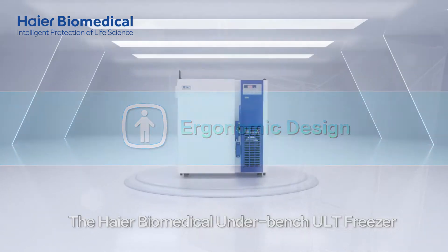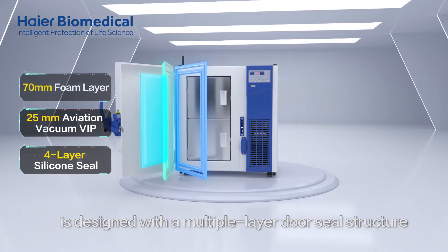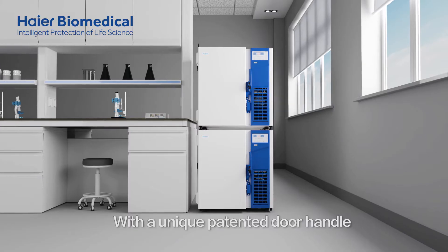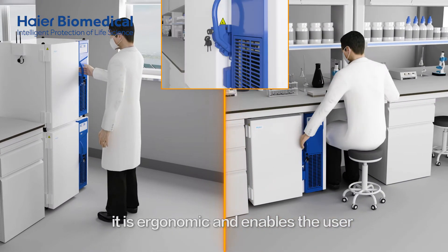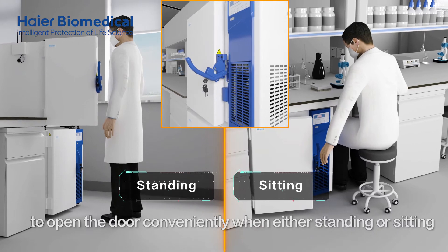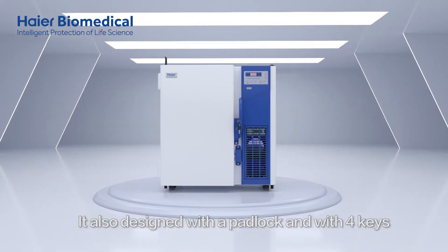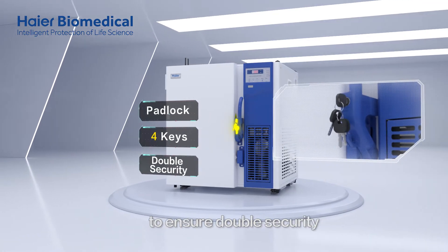The Haier Biomedical Underbench ULT Freezer is designed with a multiple-layer door seal structure, with a unique patented door handle. It is ergonomic and enables the user to open the door conveniently when either standing or sitting. It is also designed with a padlock and four keys to ensure double security.